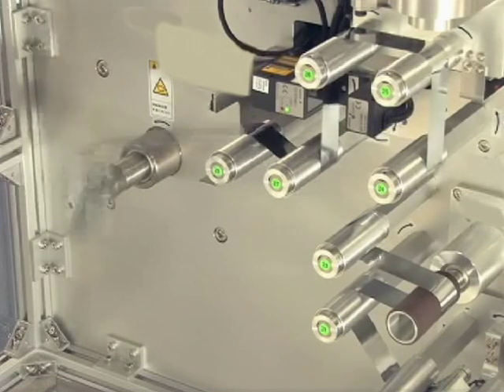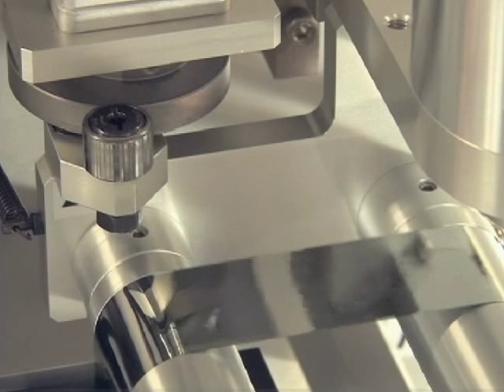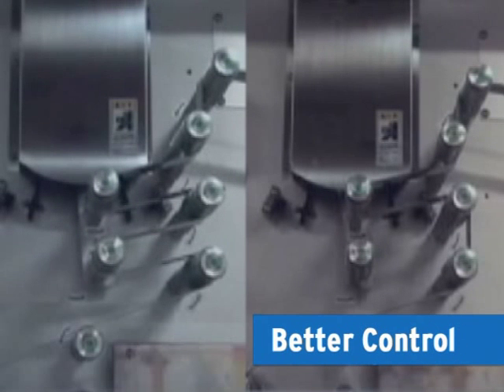Tension of the material is affected by many factors, including acceleration, deceleration, inertia, and roller friction. Using a feed-forward control strategy, the NJ controller can anticipate these changing parameters and constantly recalculate and apply new torque values, maintaining constant tension and better control.